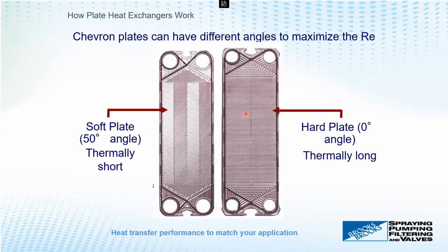If we look at this plate, which is 0 degrees, it's going to be thermally long, meaning it takes longer to go over this corrugation versus this one. Less turbulence here, more turbulence there. So you extract more heat, but you also get more differential pressure.